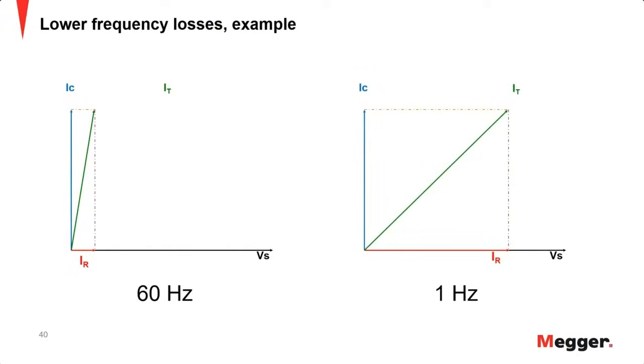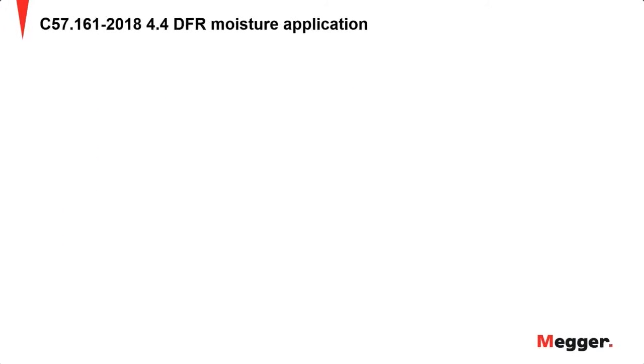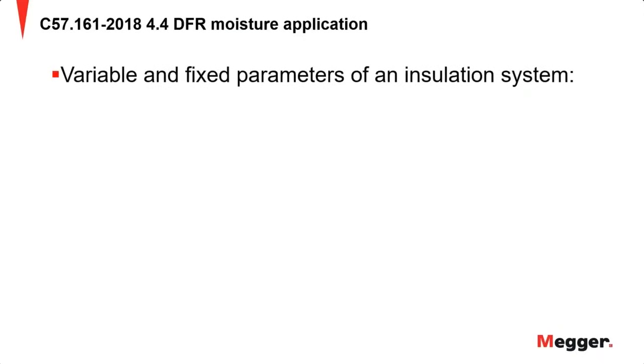And then finally, if we look at the application of moisture that comes from C57.161 in 2018, it says that there are a few variable and fixed parameters within an insulation system. What is normally fixed will be the temperature. And no, this does not mean that the transformer or bushing stays at one steady temperature during operation. This means that during your testing, that bushing is not going to change temperature significantly. If it's 18 degrees C out, then in another minute when the test completes, it's still going to be 18 degrees C.